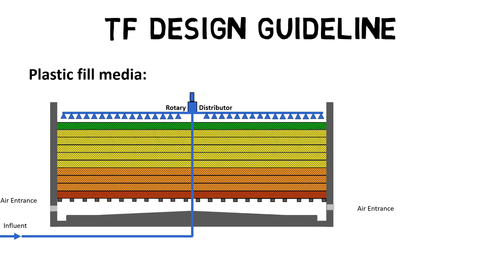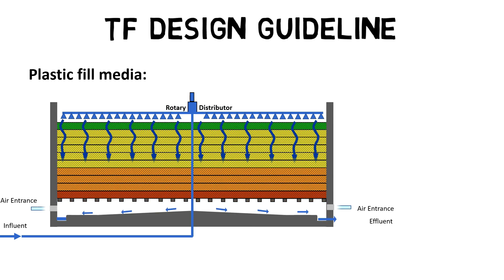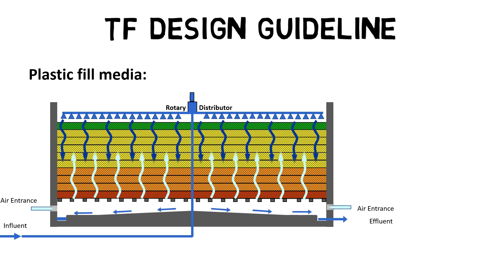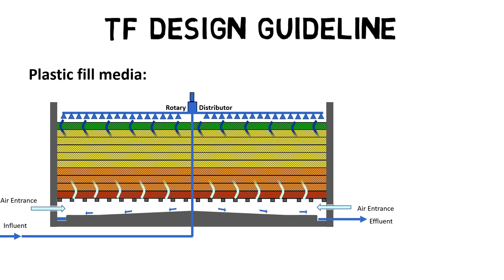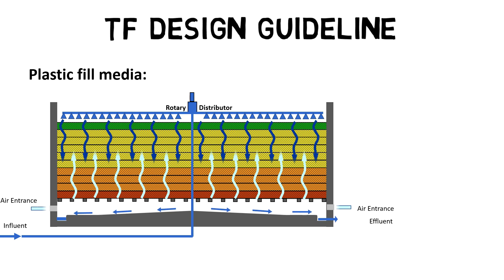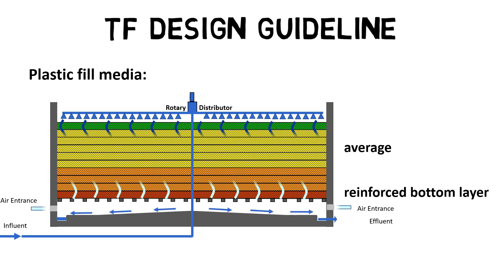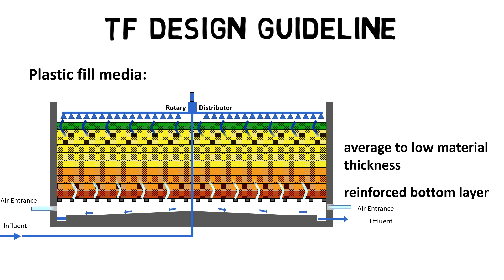To maximize the lifetime of plastic-fill media, the layer distribution must be properly designed. The material thickness of plastic-fill media foils can be varied depending on the structural loading requirements. Therefore, for a long lifetime of 30 years, the bottom layer should be reinforced, followed by average to low material thickness fill media layers, and finished with a high material thickness, reinforced top layer.